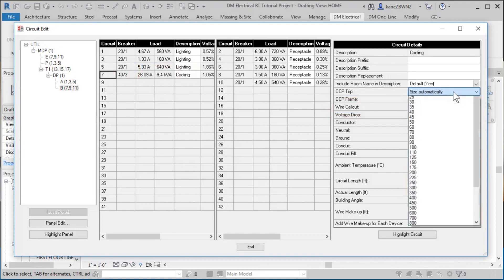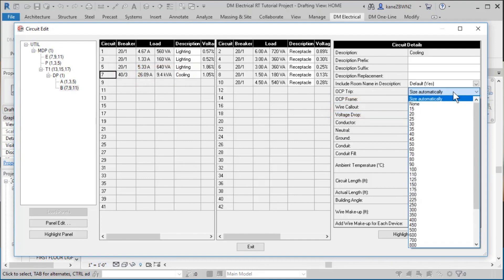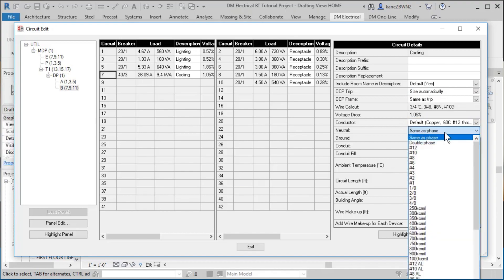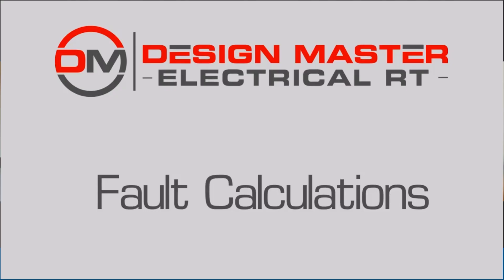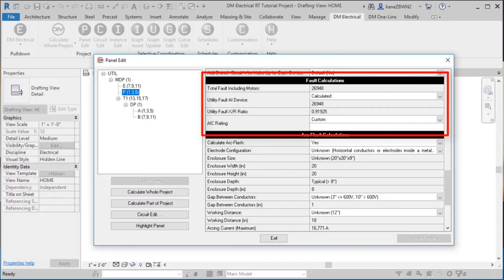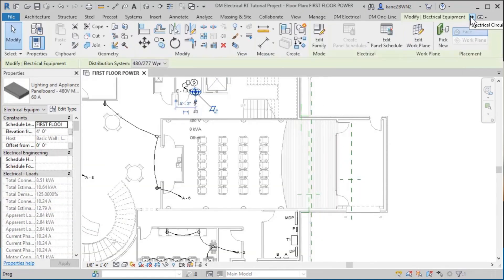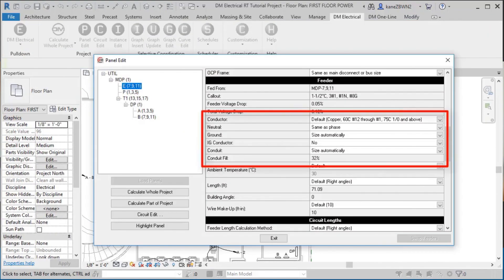None of that is handled by the 3D model. What electrical engineers really need from BIM is the Revit model — because some of it is important, you need to lay out your devices on floor plans — but then you also need to link it to the single line diagram and to the calculation model, so that you have one integrated model doing all of those things rather than three separate models in three separate spaces.